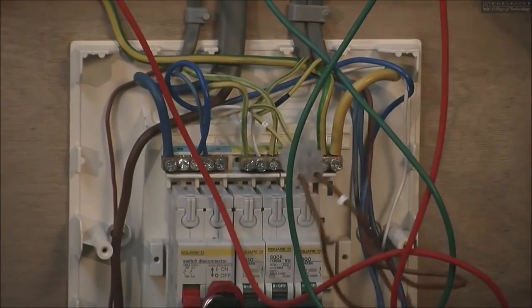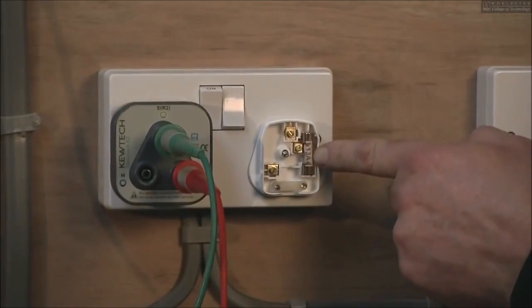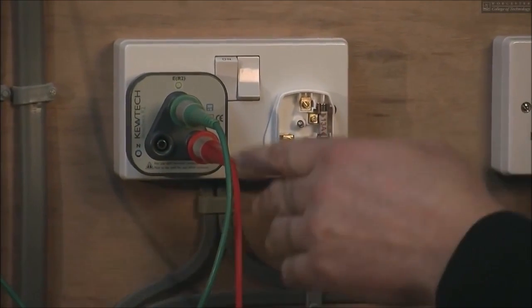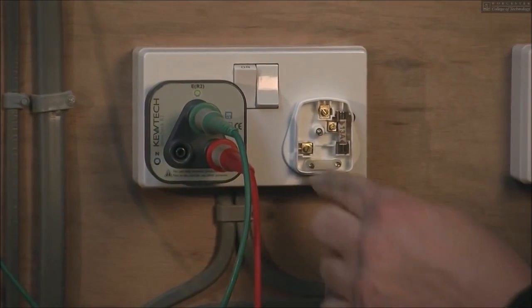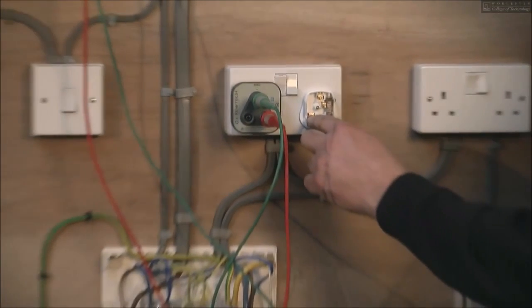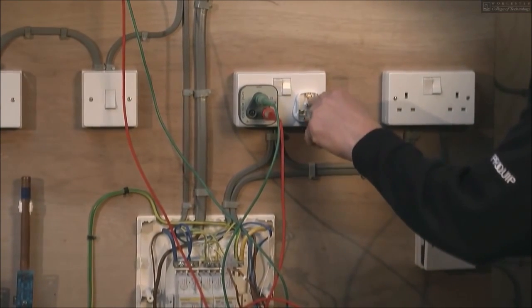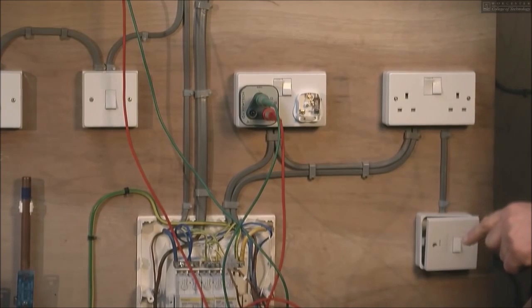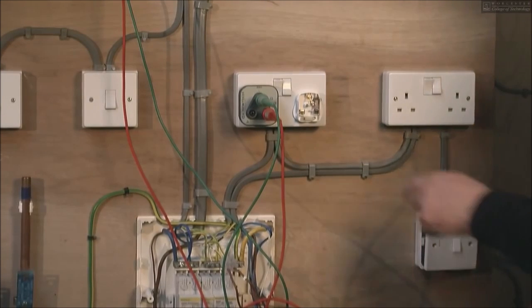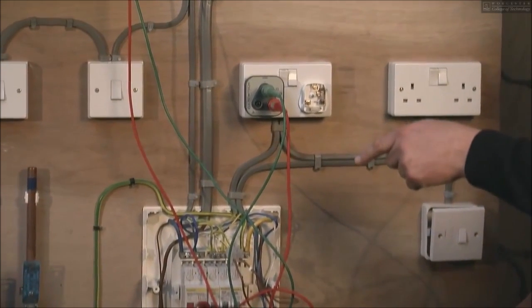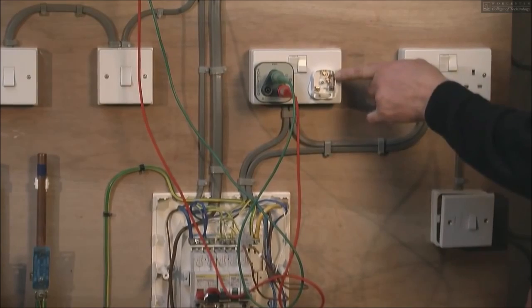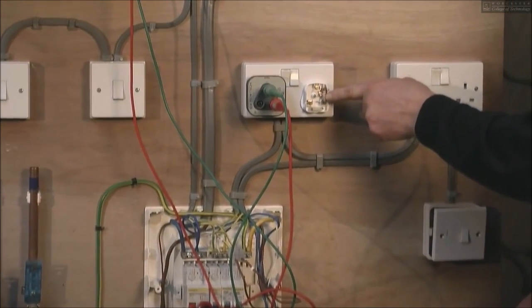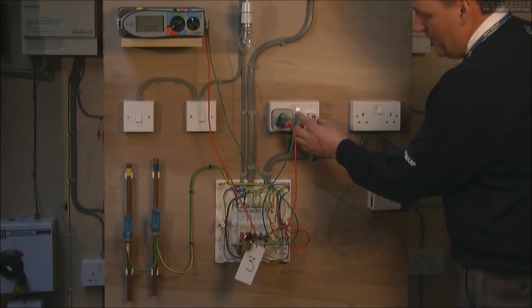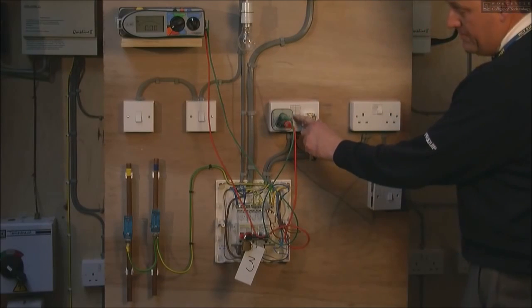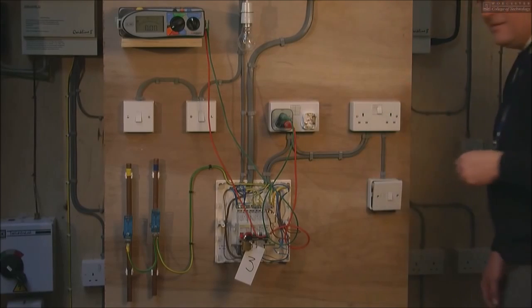So we can now establish that the brown cable is the line conductor and is on the correct side of the plug top. We can also establish that during the test we had a connection in here, which is the blue cable, establishing that it is the neutral. And vitally, the top cable has to be the CPC. It can't be anything else. So we've established continuity of CPC, which is R1 plus R2, and also the continuity of the line conductor, which is polarity. Remember, for polarity to actually work, you do need to switch the switch on, and that will supply the socket.